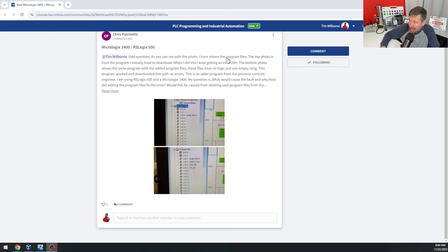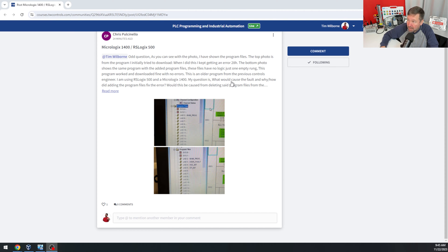I have a question. You can see in the photo that I have shown the program files. The top photo is from the program I initially tried to download. When I did this, I kept getting error 28. The bottom photo shows the same program with the added program files — these have no logic, just empty rungs. This program worked and downloaded with no errors. This is an older program from a previous controls engineer. I am using RSLogix 500 and Micrologix 1400. My question is: what would cause the fault, and how did adding the program files fix the error? Would this be caused by deleting the program files?